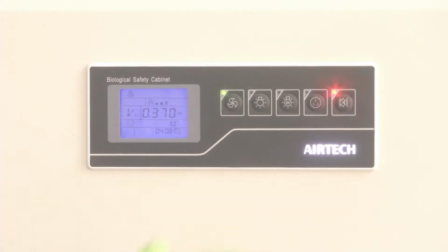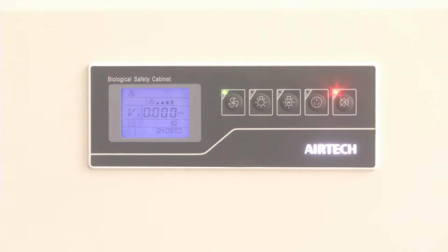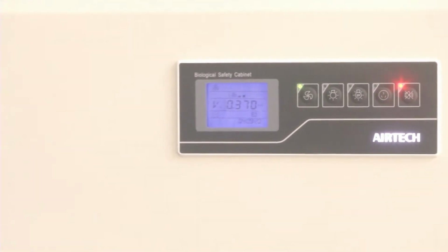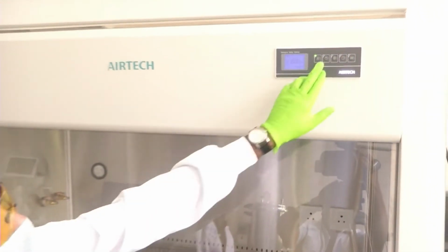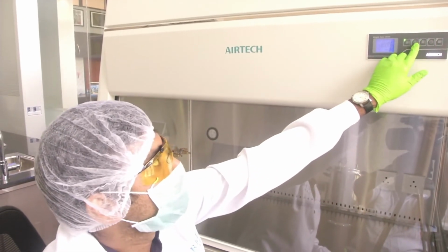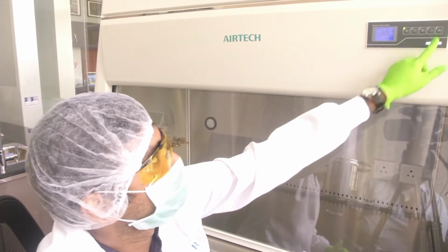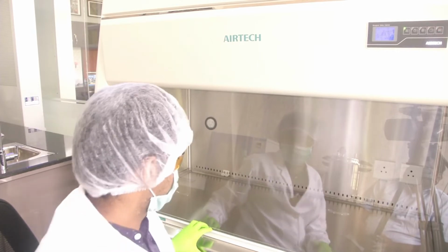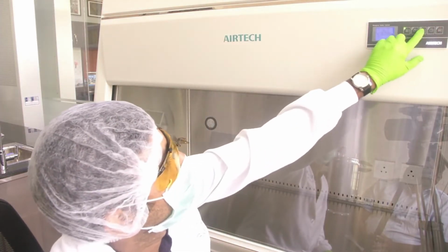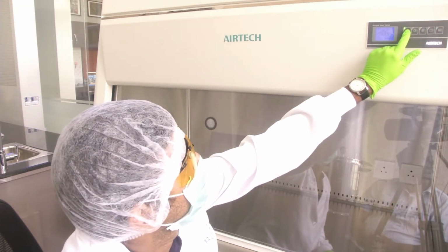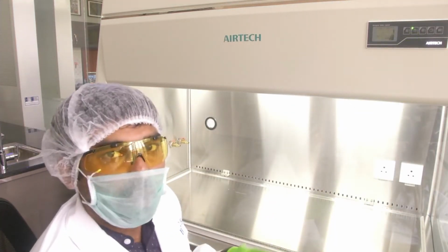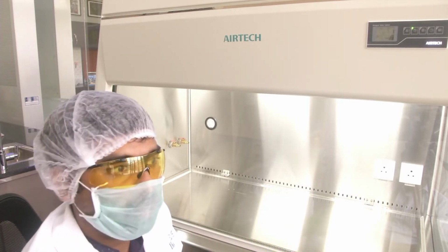Because I know that this is the issue, we can actually mute the alarm. If any other unexpected incident happens, this alarm will also ring. So there is a circulation happening inside. This circulation will constantly flush in good quality air through the hood, and also take out any chemicals that get secreted. While you work on the hood, it is advised that you always have the white light on. So let us switch on the white light. I have switched off the fan because now it has been properly cleansed. So you can work without the fan running.